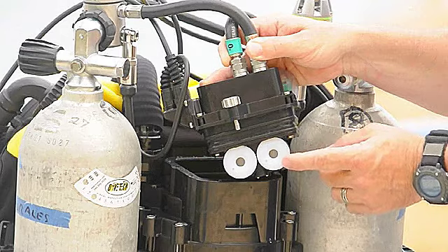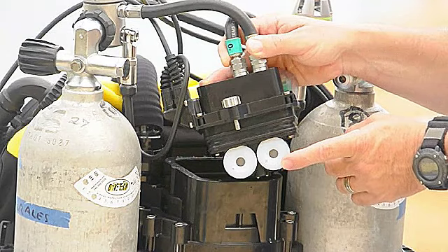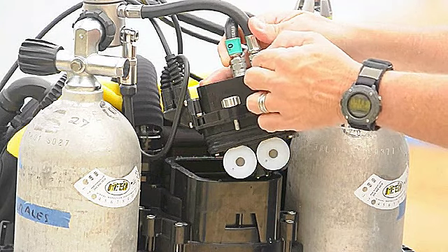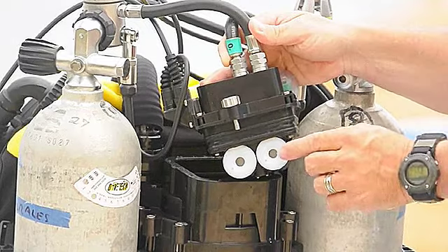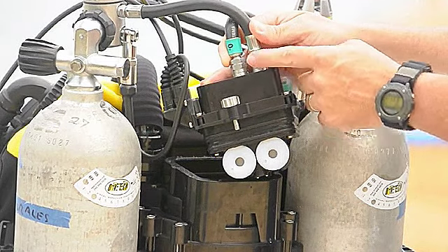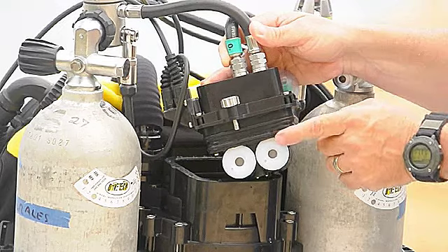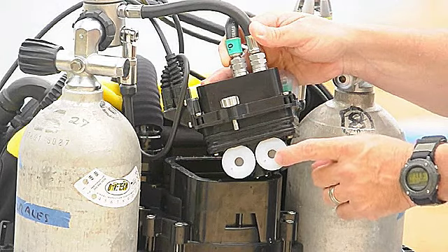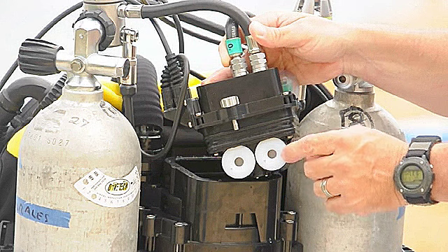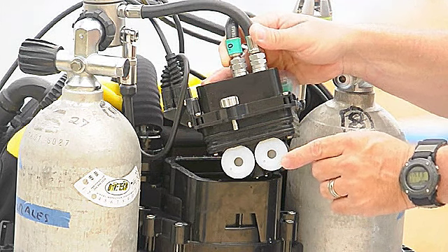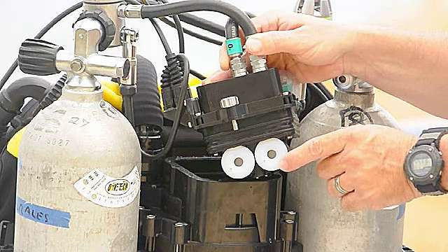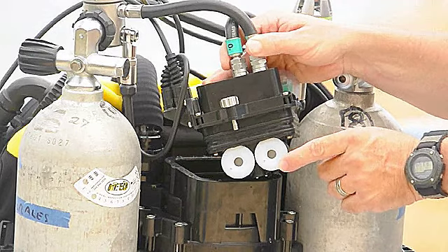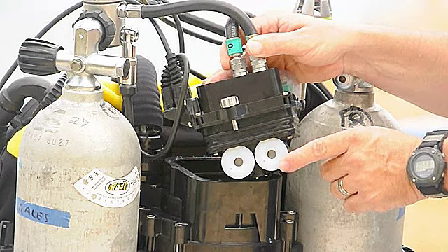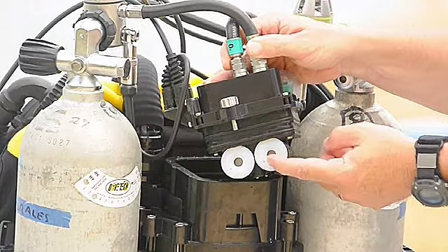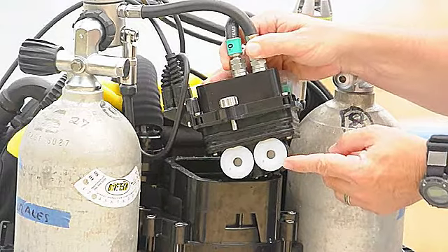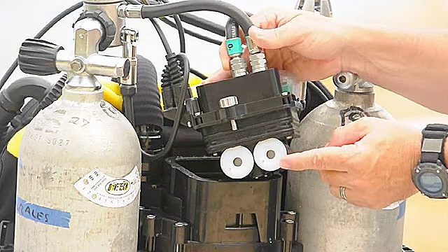And the way you have absolute confidence in an oxygen sensor is that every 5 minutes you inject a little bit of gas on it from here during the dive and watch the sensor response. So if you know what the gas concentration is and you know your current depth, you know how this sensor should respond very precisely. And so what the system does is it monitors that response and makes sure that the sensor not only can register the right amount of gas at whatever depth you're at, but that it is responding in the way that you would expect it to. So if, for example, it had condensation on it, or if the sensor started to go bad during a dive, this test would be able to pick that up very, very easily.